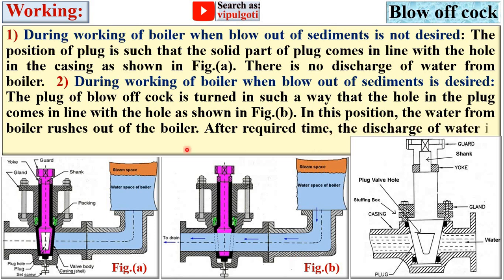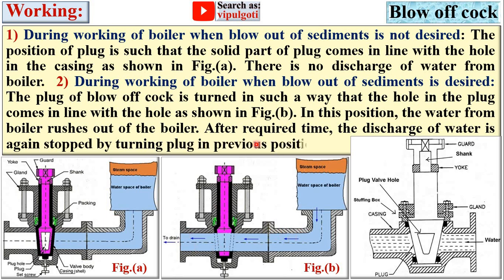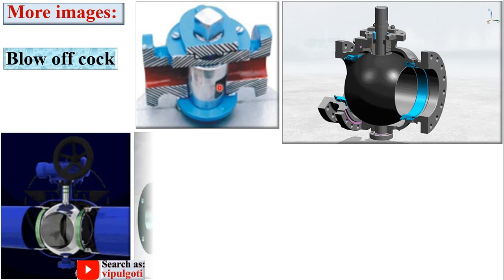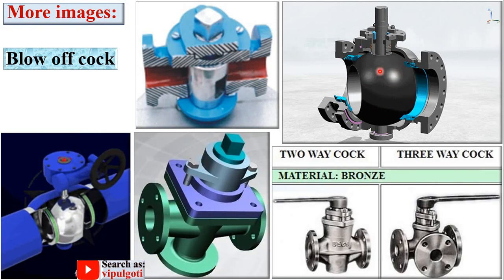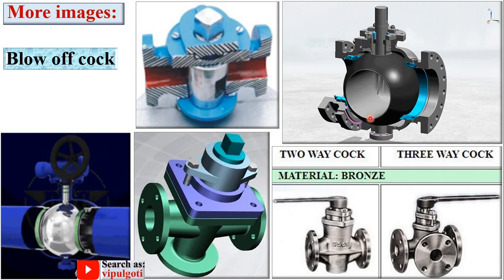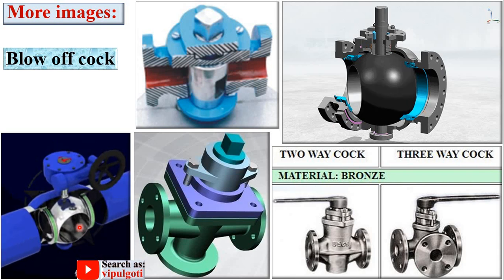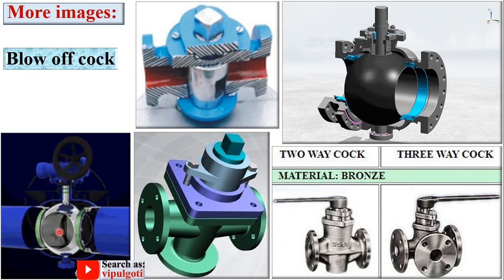In this open position, the water from the boiler rushes out. After the required time, the discharge of water is again stopped by turning the plug back to the previous position. So in the closed condition the water is held, and in the open condition the water rushes out from the boiler. Here you can see the model of the blow-off cock — it uses a conical plug, and when the hole is in line with the pipe, the fluid will flow.